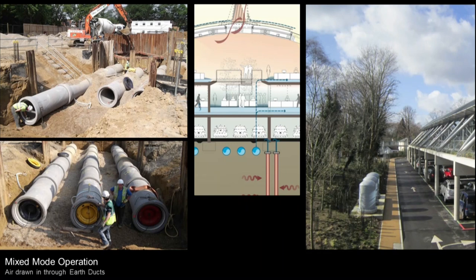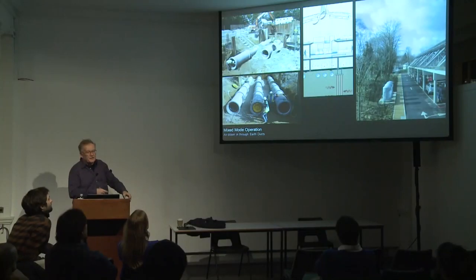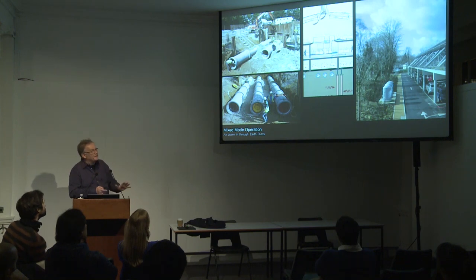Over those 80 meters, air coming in at 28 degrees on a hot day stays in contact with the ground, which is at 12 or 13 degrees all along the pipe. By the time it comes out the other end, the air is at about 17 degrees centigrade, which is fine to put into the floor as passively cooled outdoor air. This gives us full air conditioning in the building through summer without any refrigeration system at all.